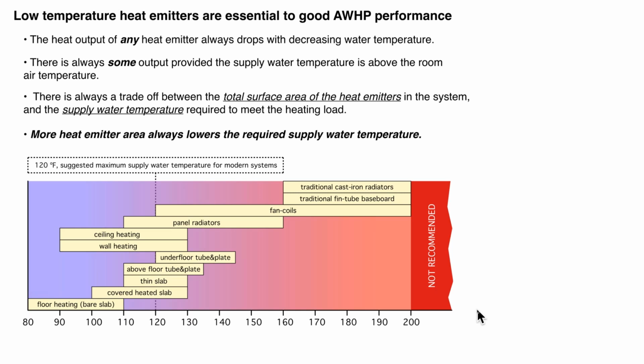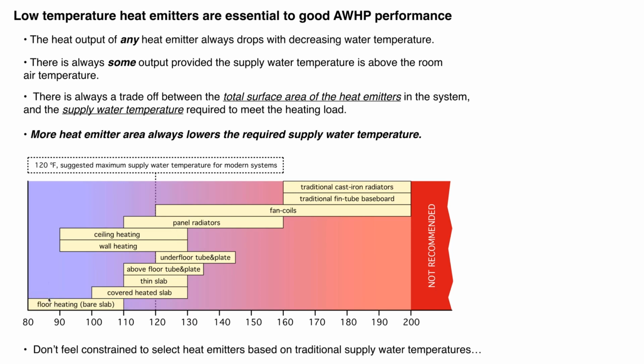Those days are gone. In fact, I would tell you most of this range, from a practical, forward-looking standpoint, is not really where modern hydronics is. Modern hydronics is over here, okay? So we're looking at a range like this, and there's a lot of application here. I've got ceiling heating, wall heating, and several types of floor heating here. One of the ideals is a bare slab. When I say bare slab, it could be painted, it could be stained. If you've seen some of the stained concrete slabs, they're absolutely beautiful. So minimizing that surface R value is important.